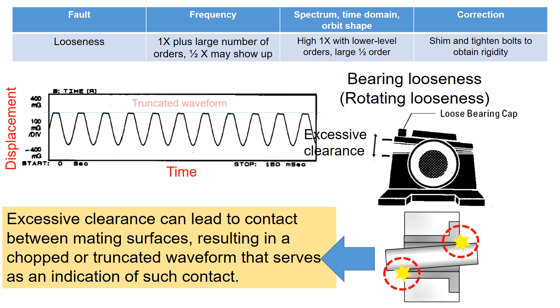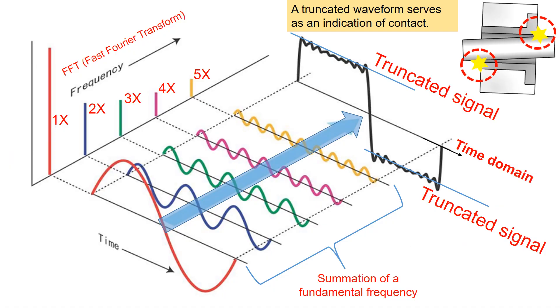Excessive clearance can lead to contact between mating surfaces, resulting in a chopped or truncated waveform that serves as an indication of such contact. For example, the truncated signals in the time domain indicate the contact.